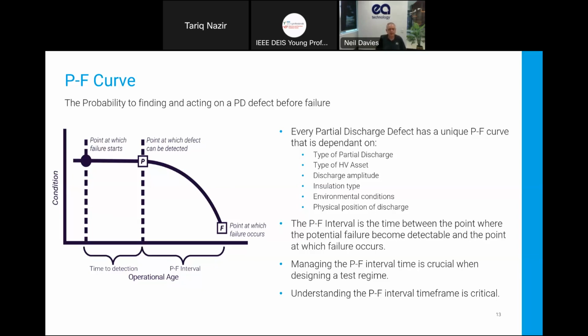But PD is, as we've seen, there's a number of different types, and every partial discharge defect will have a unique P-F characteristic and curve. It's going to be dependent on the type, the HV asset involved, so different designs will have different capability withstanding, if you like, PD, the amplitude, the insulation type. If we had surface discharge on a polymeric bushing and surface discharge on a porcelain bushing, the porcelain bushing is one that we're unlikely to get any real concern about, particularly in the open siding, because it's very much more tolerant. So the insulation type makes a big difference.